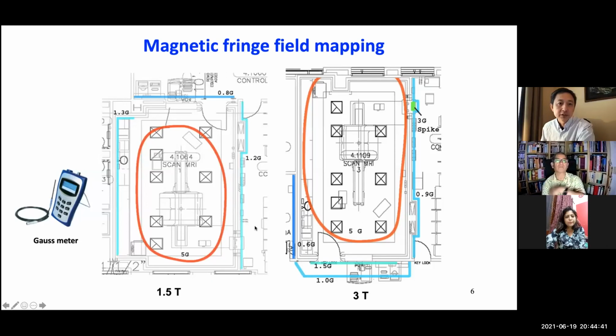And after MRI installation, there is a magnetic field. The so-called fringe field is the magnetic field extended outside of the MRI. I think everyone who has learned MRI knows the 5 Gauss line is very important for MRI safety and control. So once the scanner is installed and the field is ramped up, we have to map the fringe field, at least to map where the 5 Gauss line is.